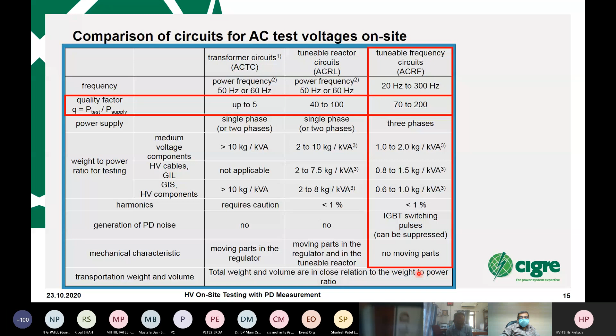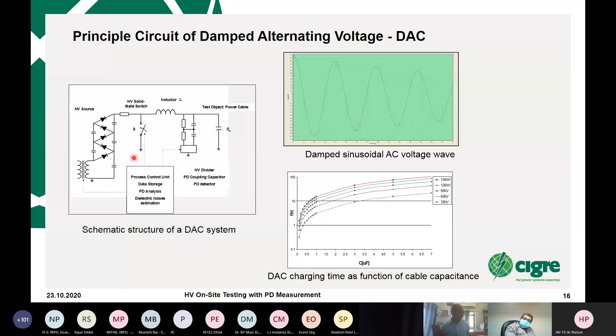The other technology is AC DAC. This means that the test object, which is a cable, for example, is capacitive, like shown here. Now my pointer is doing strange things, but nevertheless, the cable is charged by DC voltage, which is shown on the left-hand side. It will take some time depending on the cable length or the capacitance of the cable, which is shown here on the bottom in microfarad, and it could be several seconds or several minutes. For medium voltage, it's okay to stress the cable with DC, and then you short circuit the cable via the inductor to ground. In combination with the inductor and the capacitance, this circuit starts to oscillate and gives the damped sinusoidal AC voltage shape.